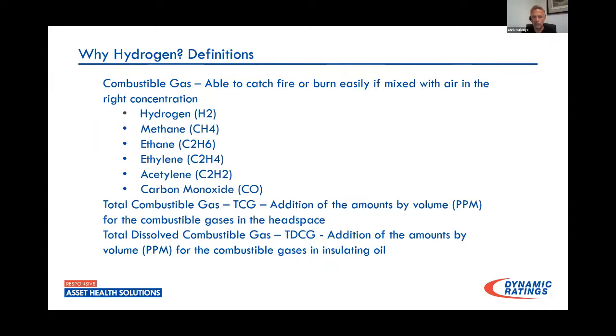So by pulling these DGAs, once we had this out of service, we've had our warning, we get our transformer out of service, we pull our DGAs, and we can pretty much determine, well, there's a lot of gas saturated in oil in, let's say, the switch compartment for this transformer, because again, with the way gases are, the solubility rates, where it's being generated, it's where the DGA is really going to show those high values of that gas. So that would be what I would recommend. And again, if you want to go through, for another time, doing analytics concerning what the ratios of gases are as to what type of problem you would have, also looking at carbon monoxide and carbon dioxide, determining some of your cellulose involvement using those, that would be a topic for a whole other discussion, and we don't really have time to get into that too much today. But that would be the primary thing I would suggest we go through to determine.